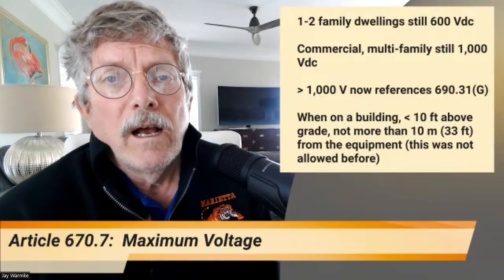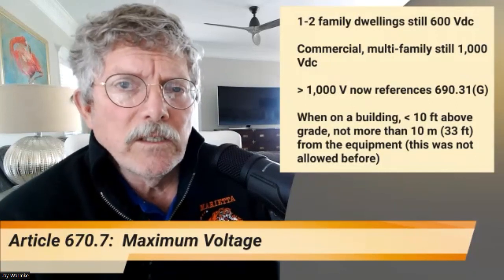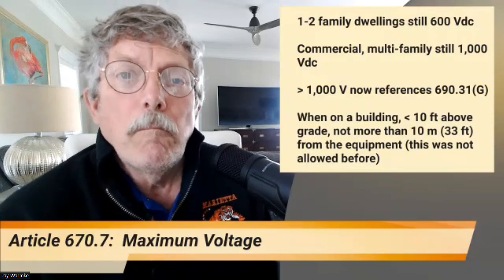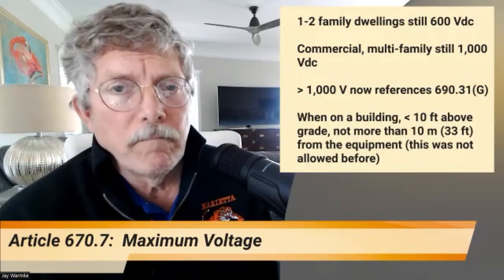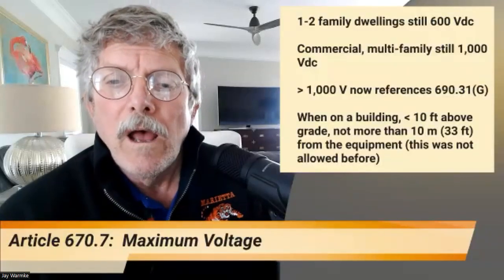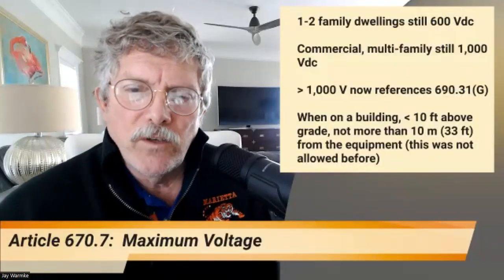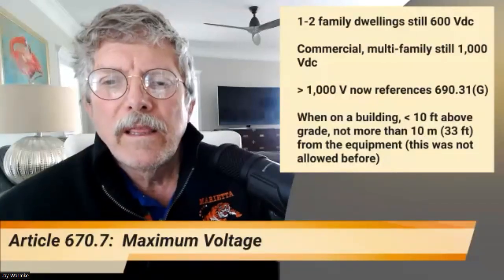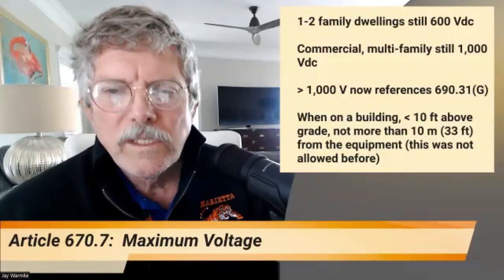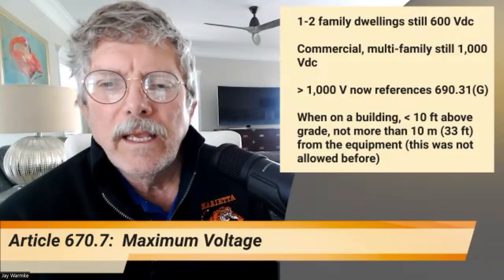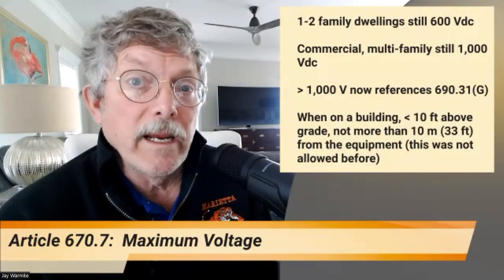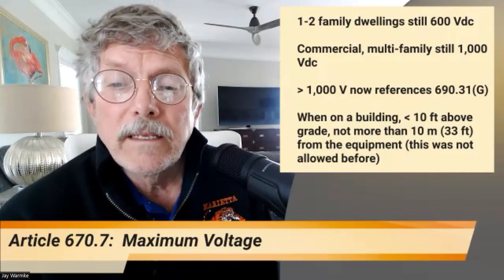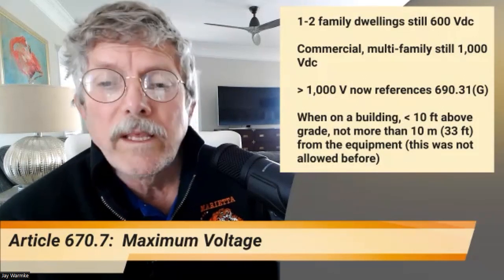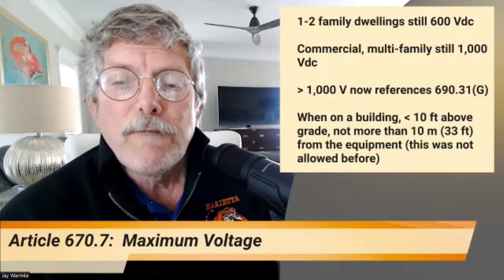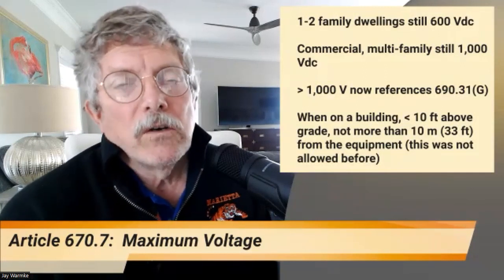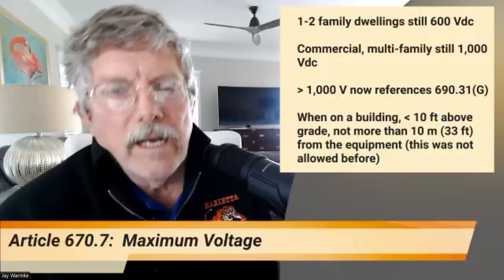So it's kind of a solution, at least in the PV industry, in search of an application. But of course, there are other applications out there, not photovoltaics, that deal in those higher voltages. But they've defined then, if you do put a system that is greater than 1,000 volts on a building, then it has to be less than 10 feet above grade. And the panels themselves cannot be more than 10 meters or about 33 feet from the equipment to which they're connected. So in this case, they're talking about unoccupied buildings.